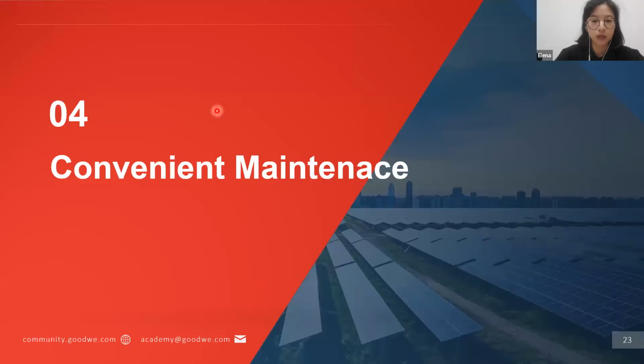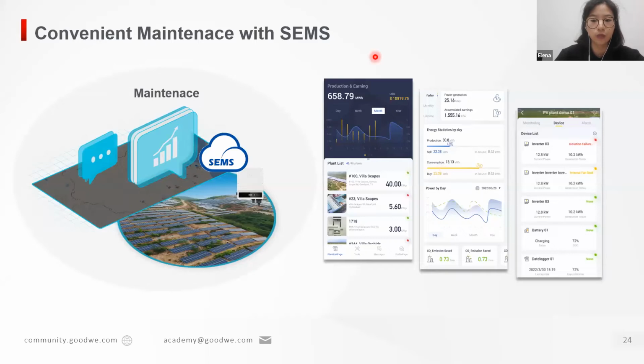After the system commissioning, the remote monitoring of the system will be important for the maintenance. We use our SEMS portal to do some remote monitoring. So the data of the inverter needs to be uploaded to the server for the solar system monitoring. For a single inverter, we can directly use wireless communication modules like Wi-Fi module, LAN module. And for multiple inverters, GoodWe provides a smart communication box to collect the inverters' data and then communicate with the server. Once the inverter data are successfully uploaded, users can remotely monitor the real-time operation data and view history data through GoodWe's SEMS portal, app, or website.